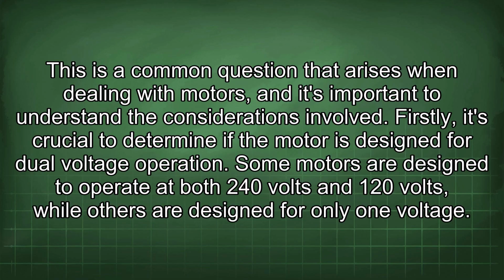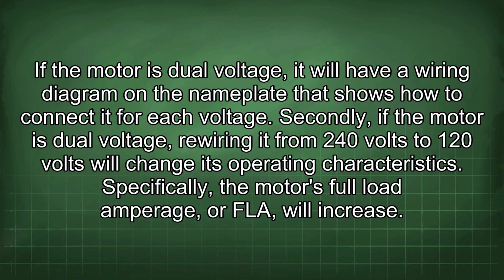Firstly, it's crucial to determine if the motor is designed for dual voltage operation. Some motors are designed to operate at both 240 volts and 120 volts, while others are designed for only one voltage. If the motor is dual voltage, it will have a wiring diagram on the nameplate that shows how to connect it for each voltage.